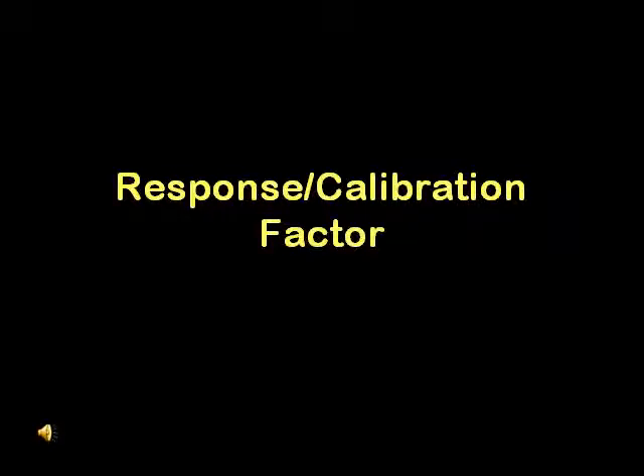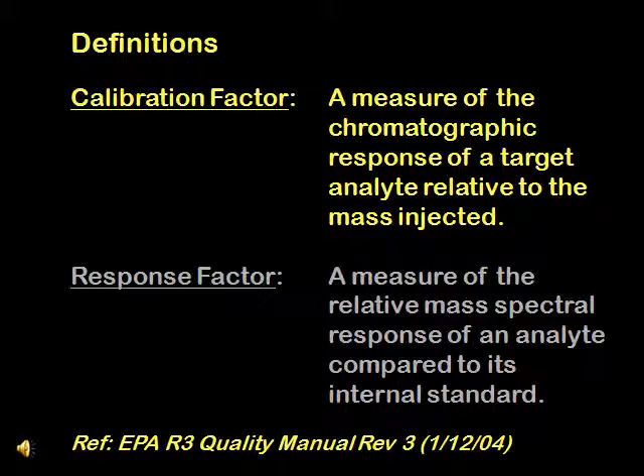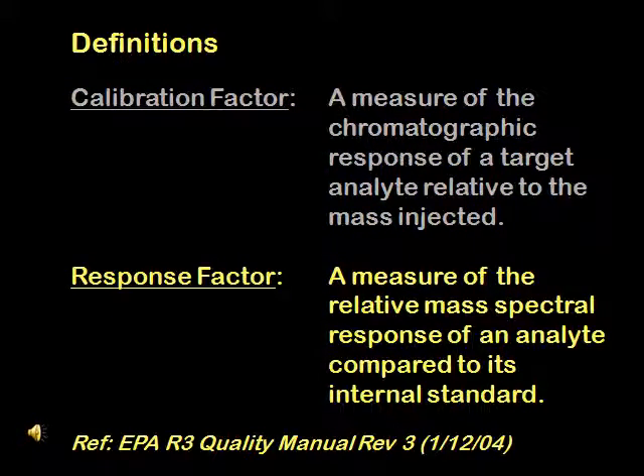Response or calibration factors are commonly used in environmental laboratories. Calibration factor is a measure of the chromatographic response of a target analyte relative to the mass injected, whereas a response factor is a measure of the relative mass spectral response of an analyte compared to its internal standard.